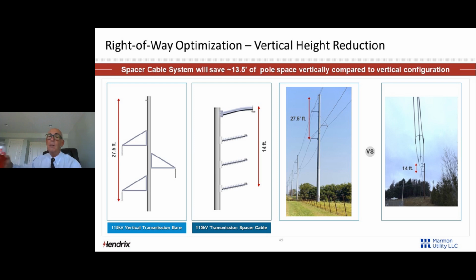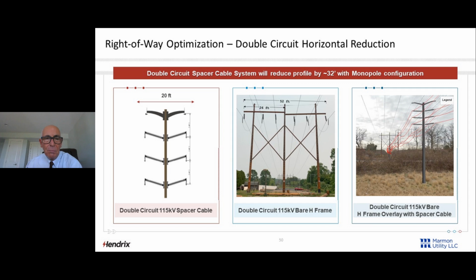How about vertical height reduction? If I look at the drawing on the left, is a vertical transmission, 115 kV bare, 27.5 feet. We go with spacer cable, it's 14. So now I'm saving 13.5 feet. Do you want to save 13.5 feet vertical height reduction? What is that savings? Are you saving on poles? What else are you saving on? Aesthetics. How about a double circuit monopole? Now you're saving 32 feet side to side width on that right of way. That's a heck of a lot of space.